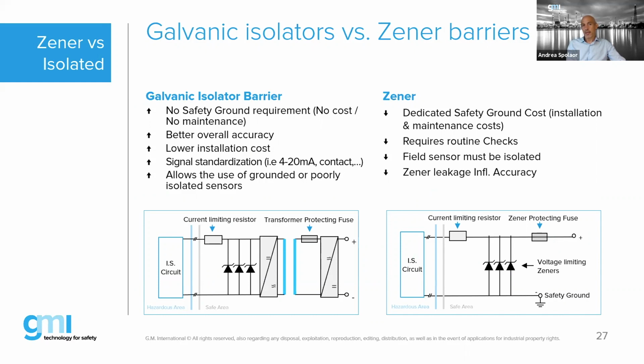So why are galvanic isolators safer than Zener? As we said, the isolator doesn't need any safety ground, so there is no cost for that. There is better accuracy, because the diodes can have some leakage. And there is a low installation cost, as we say. The sensor doesn't need any ground, and the isolator itself doesn't need any earth connection.